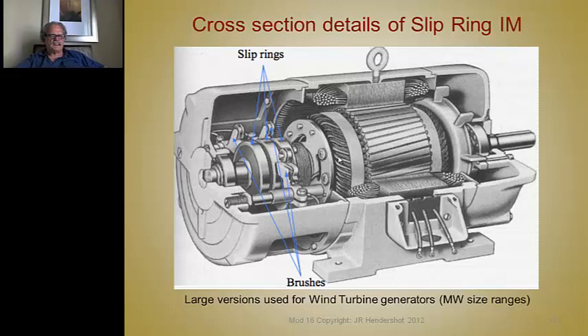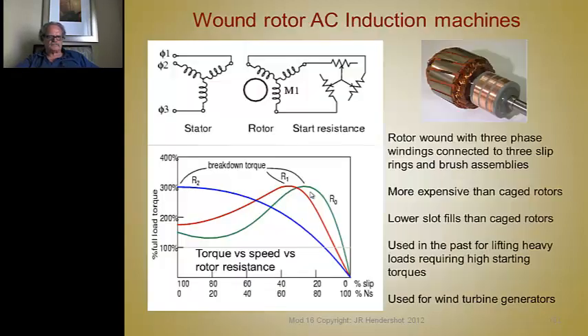So the same mechanical configuration of the machine, the number of turns are different of course, is used for wind turbines, so that this winding is excited by a 3-phase AC inverter, taking power off the grid, but only about 1/3 of the rated power of the AC generator is taken off the grid. So you use 1/3 of the power, but you generate the other 2/3. So you generate a lot more than you use. So that's one reason why they're so popular. Plus, they're easy to synchronize to 60 hertz.